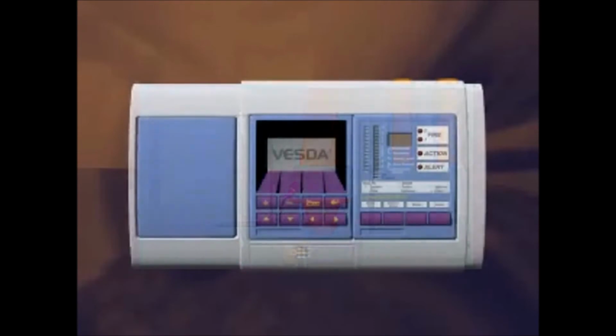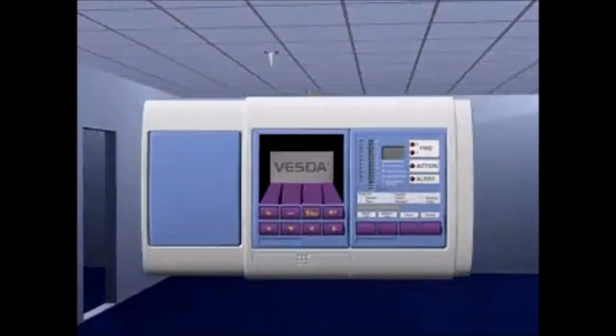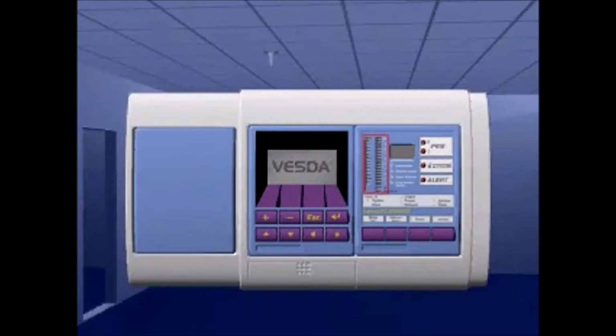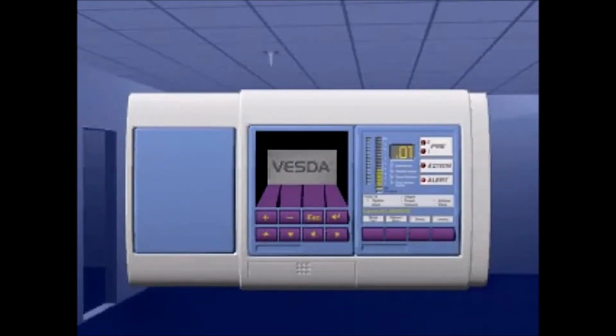The sample proceeds into the chamber where it is exposed to a controlled laser light source. Even extremely low levels of smoke particles present in the air sample will cause the laser light to scatter. This light scatter is instantly detected by a unique configuration of light receiver circuitry, optimized for a wide range of smoke types. The resulting signal is immediately processed and presented via a bar graph display, alarm threshold outputs, and/or graphic display. The VESDA system has 4 smoke alarm threshold levels: Alert, Action, Fire 1, and Fire 2. The sensitivity for each alarm level can be automatically programmed or manually set to a suitable level to fit the condition of the site and to minimize unwanted nuisance alarms.